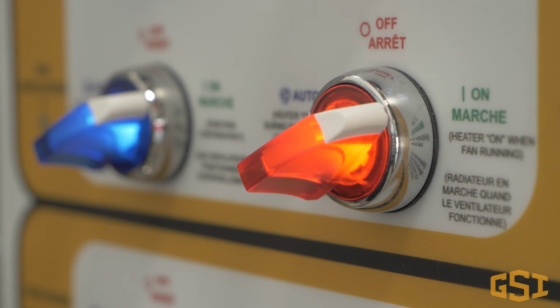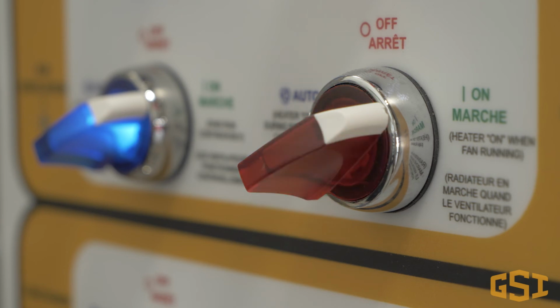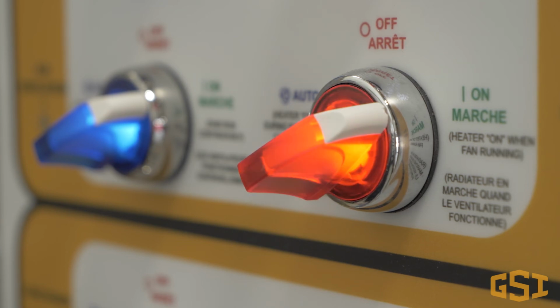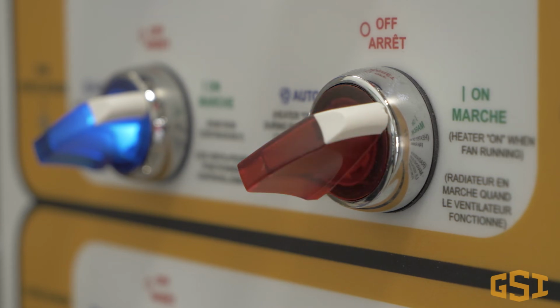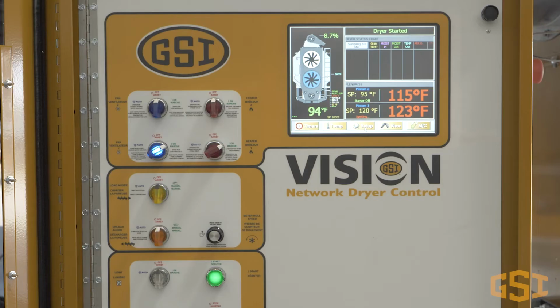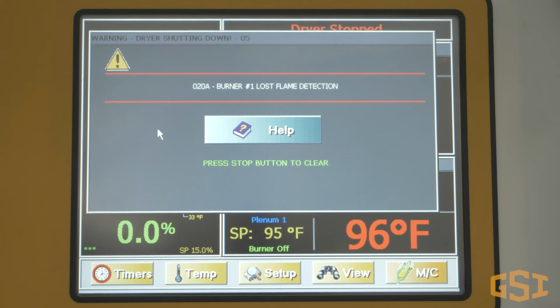What if the light blinks? What does that mean? Anytime the light goes out, the connection between the flame probe and flame has been broken. When the flame probe is adjusted properly, the light will never blink. Let's review this because it is especially important. If the light blinks, it indicates that the flame has missed the flame probe for just a second. If the connection is reestablished quickly enough, the burner will continue to run. If not, the dryer will go into a loss of flame shutdown.